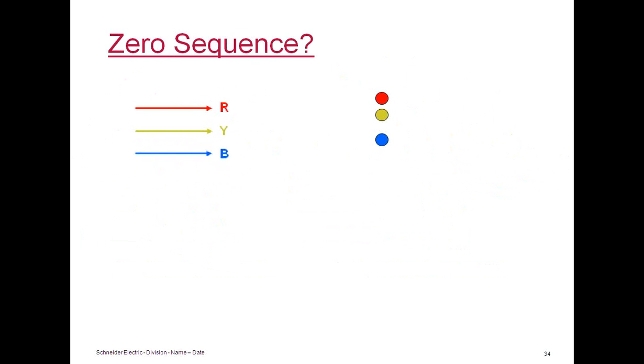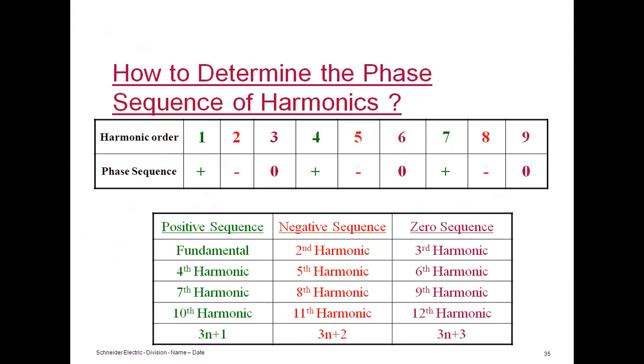This is a small table to understand the sequence in harmonics. We just write down the harmonics from 1 to 9. One is the fundamental, the normal frequency, and then we have 2, 3, 4, 5, and we write down plus, minus, 0, and repeat the same thing, plus, minus, 0, here. Anything under plus is called plus sequence, anything under minus is called minus sequence.